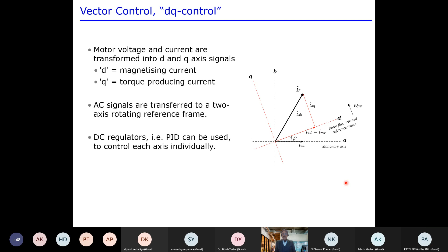This is the flux vector control, and here you see the speed controller for Q axis current, and the flux controller, which takes care of the motor flux estimated from the motor model. Then from the needed flux reference, there is a D axis required current.